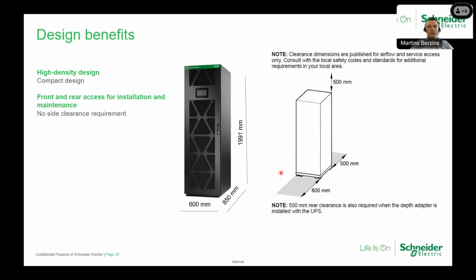Regarding the installation, as I said, the UPS is very compact, 600 millimeters wide, 850 millimeters in depth, and when installing, no side space is required. The UPS is maintained fully from the front and the back. In the front you need an additional 800 millimeters clearance for maintenance, and on the back also 500 millimeters for maintenance and airflow, and 500 millimeters on top. It's for the cable entry reasons.